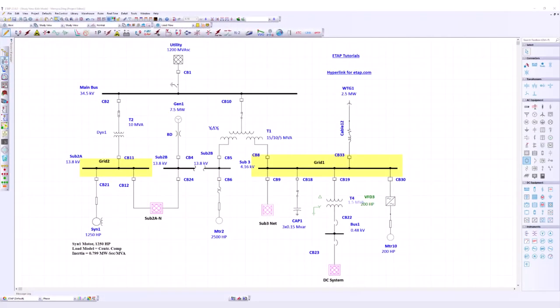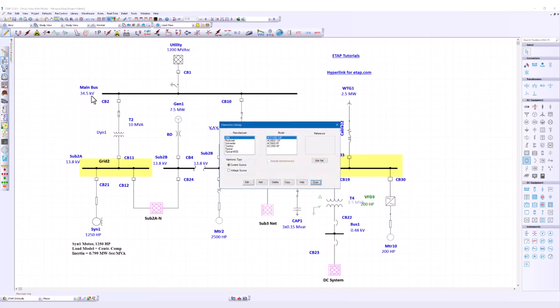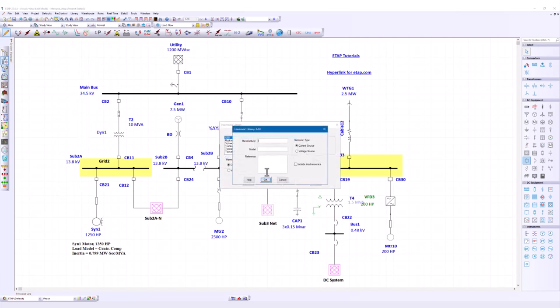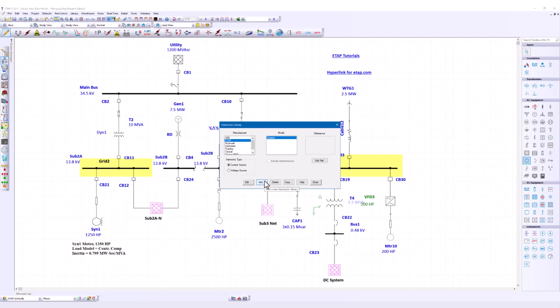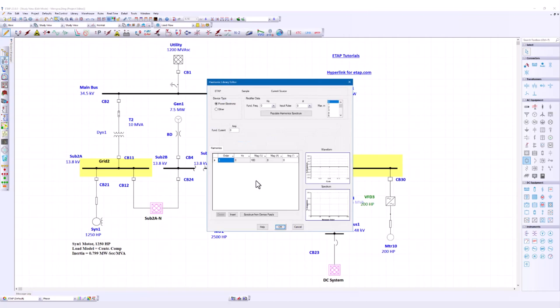When you receive a harmonic test report from the manufacturer, the first thing to begin the harmonic modeling is to plug the data into a harmonic library. You can go to the library, harmonics, and we can add a harmonic library by selecting whether it is a current source or voltage source. For now, I'm going to select a current source, name it ETAP, and the model name is sample. Click OK. Now you will see the entry has been added. Now let's click on the Edit button, and here opens the harmonic library editor. Let me specify the fundamental frequency is 60 Hz.